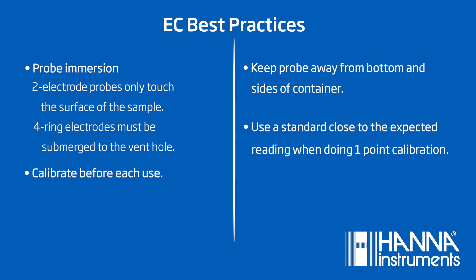Calibrate daily if you're using the probes daily. Otherwise, calibrate the probe prior to use. Regardless of the probe being used, keep the position of the probe in mind when taking a measurement. A one-point calibration, where the standard is close to the expected value, is common when calibrating your probe. One thing to know is that the calibration standards have no buffering capacity and are very easily contaminated.